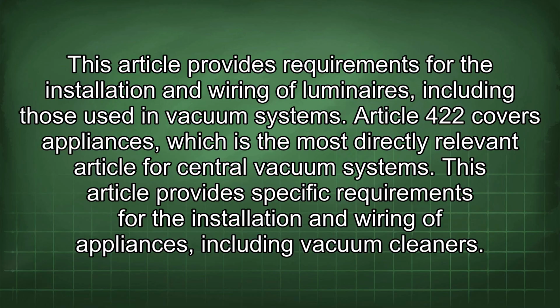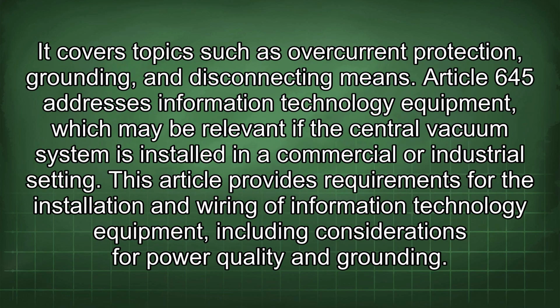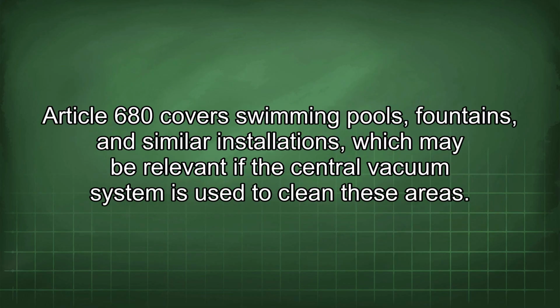Article 422 covers appliances, which is the most directly relevant article for central vacuum systems. This article provides specific requirements for the installation and wiring of appliances, including vacuum cleaners. It covers topics such as overcurrent protection, grounding, and disconnecting means. Article 645 addresses information technology equipment, which may be relevant if the central vacuum system is installed in a commercial or industrial setting. This article provides requirements for the installation and wiring of information technology equipment, including considerations for power quality and grounding. Article 680 covers swimming pools, fountains, and similar installations, which may be relevant if the central vacuum system is used to clean these areas.